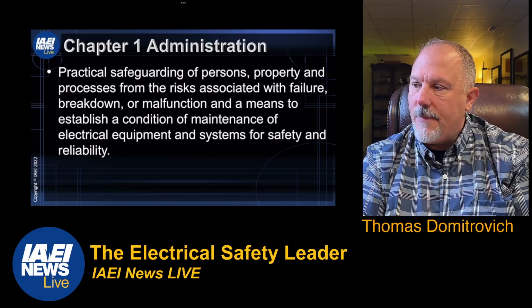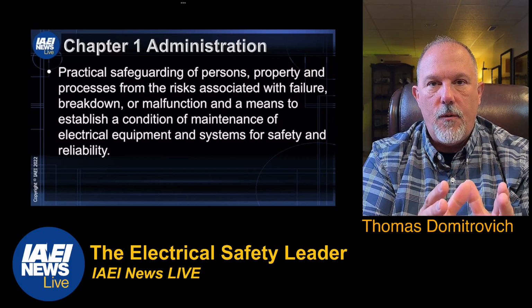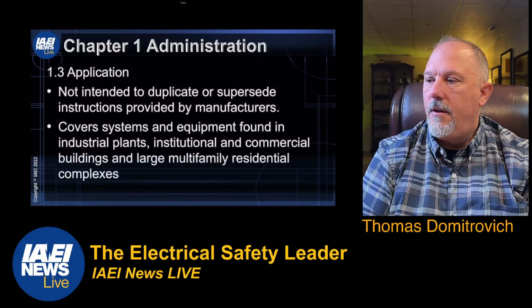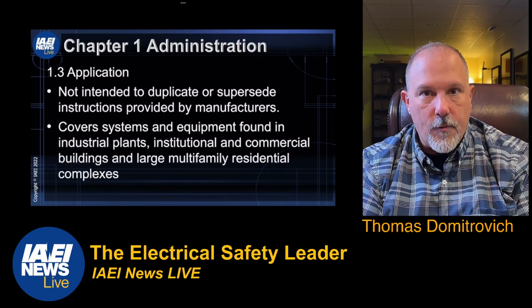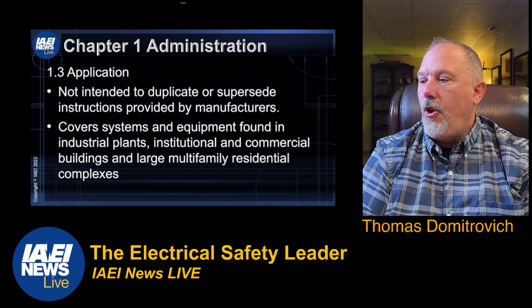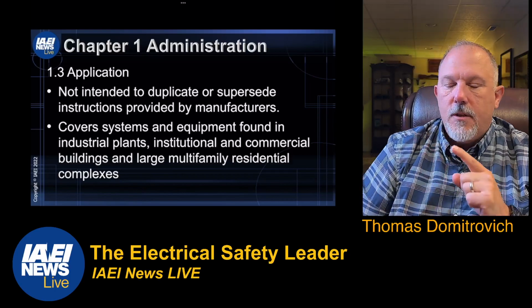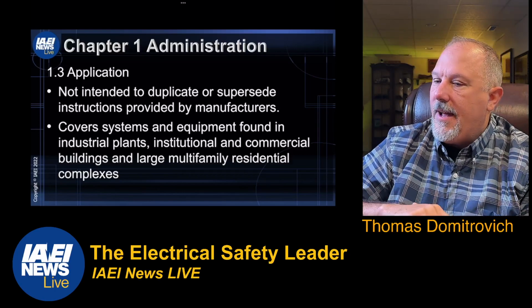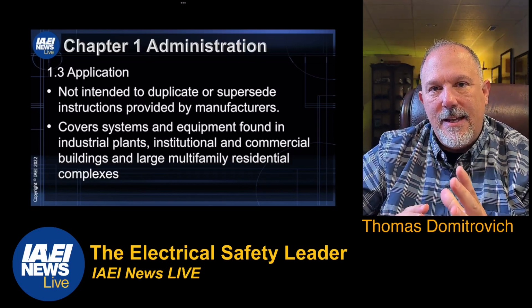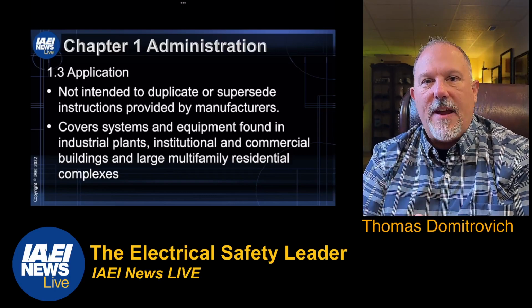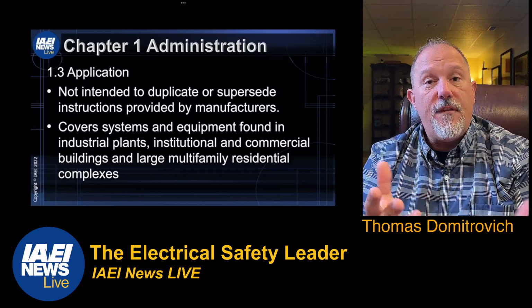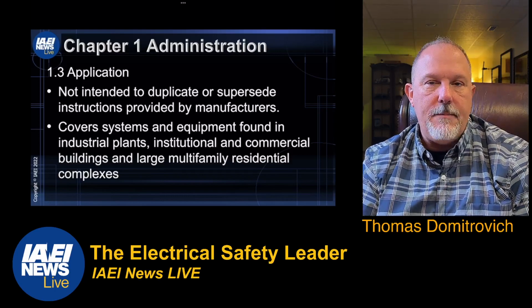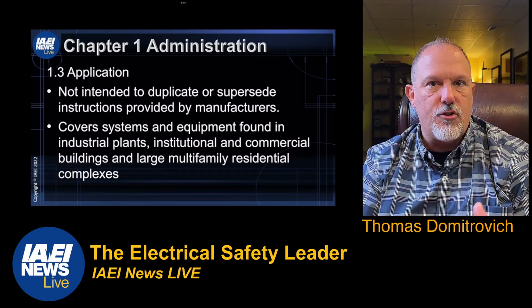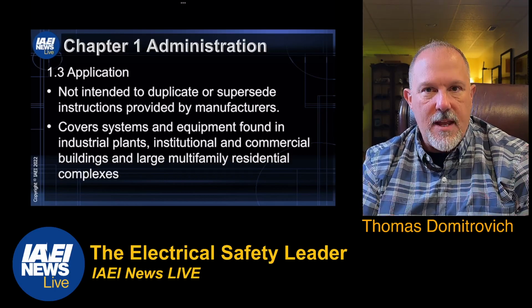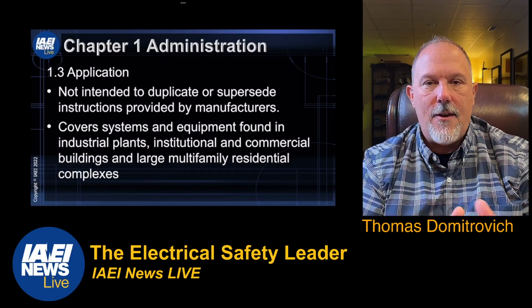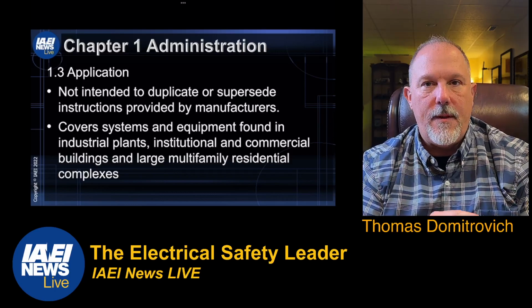So Chapter 1 tells us the purpose of the document you are reading. This is an important piece: the intent is not to replace manufacturer's instructions. So if we're talking grounding and bonding—dealing with a panel board, switchboard, switchgear, transformers, whatever it is—if the manufacturer's instructions tell you how to maintain the grounding and bonding in that equipment, you follow that.